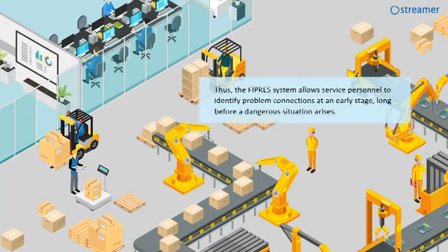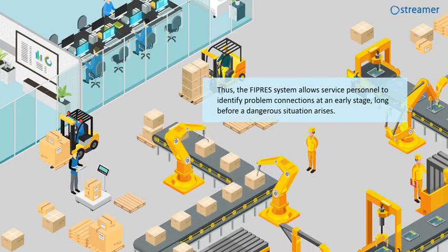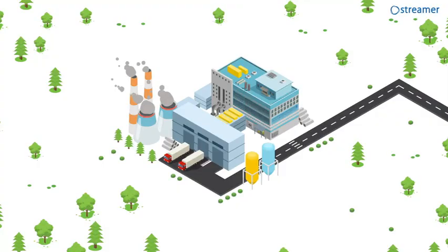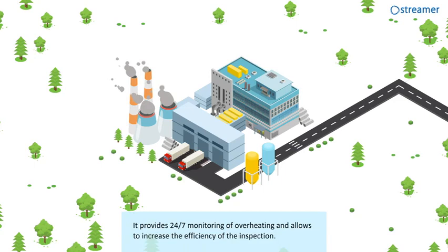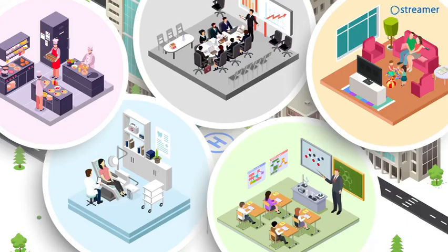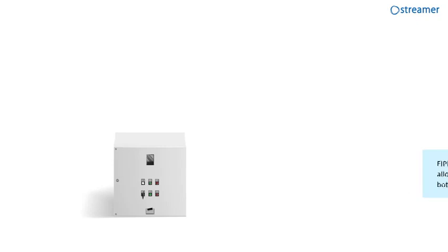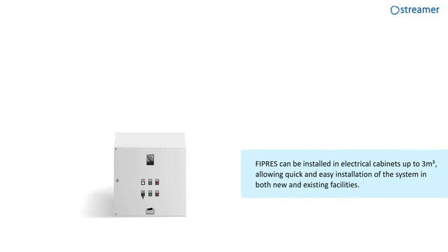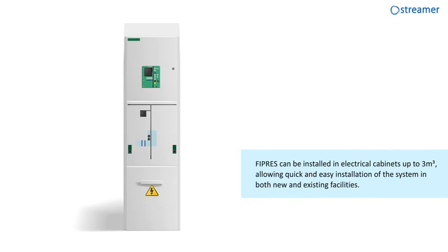Thus, the FIPRES system allows service personnel to identify problem connections at an early stage, long before a dangerous situation arises. It provides 24/7 monitoring of overheating and allows to increase the efficiency of the inspection. FIPRES can be installed in electrical cabinets up to 3 cubic meters, allowing quick and easy installation of the system in both new and existing facilities.